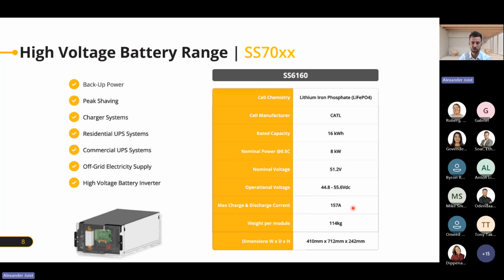Which is a bit different to what it was before. Before we had 200 amps charge and discharge current, but now it's a bit lower. It is 157 amps. So we just need to be careful in designing our systems. Also with the 14.3, the 16 kilowatt hour wall mount residential product, it's the exact same. So just be careful with that. If you parallel that with any inverter, with your Victrons or anything like that, just make sure that the charge and discharge current matches your inverter.